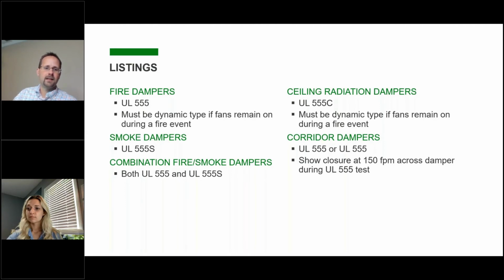Another thing is you see, for instance, the UL listing is different for ceiling radiation dampers than for fire dampers. So you can't just apply a fire damper in a ceiling radiation damper application. And that's another good reason to use proper terminology on a project. You don't want to say, hey, put a fire damper at this grill, when what you really need by code is a ceiling radiation damper. Most of the time, everybody knows what is intended and it gets installed okay, but to prevent possible miscommunication or issues in the field, use proper terminology when you're applying these dampers.